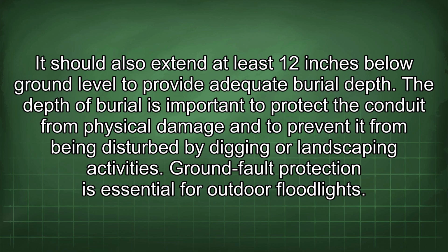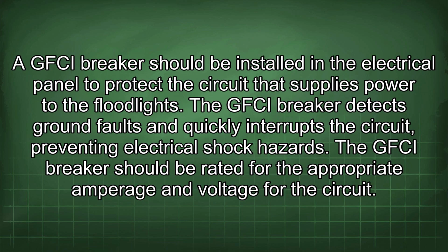Ground fault protection is essential for outdoor floodlights. A GFCI breaker should be installed in the electrical panel to protect the circuit that supplies power to the floodlights. The GFCI breaker detects ground faults and quickly interrupts the circuit, preventing electrical shock hazards. The GFCI breaker should be rated for the appropriate amperage and voltage for the circuit.